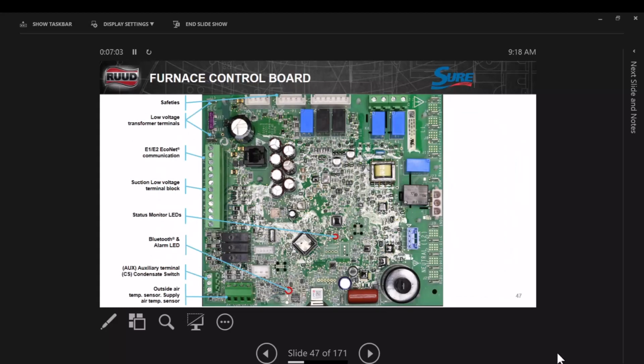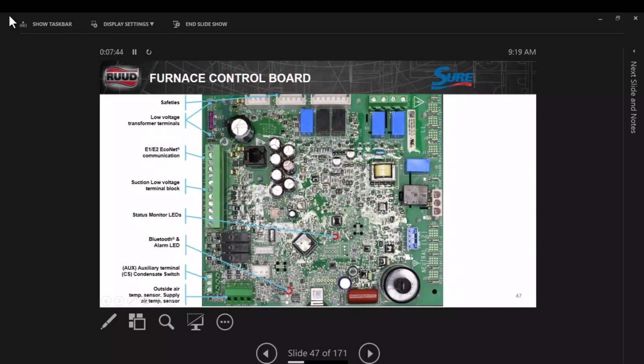On the furnace control board, you see at the top row, that's all the safeties coming in up here at the top. We have our low voltage terminals coming down the left side there. And then we have our terminal block. This is where your E1 and E2 communication circuit control is going to go, and your 24 volts to your thermostat. All that's going to go there. Right down here, you see the LEDs, the Bluetooth LEDs here. Auxiliary terminal switch. Now, the auxiliary is where we're going to hook our condensate switch up. Because this unit is a communicating unit, even though it's a regular thermostat, it's still communicating. We cannot break any of the thermostat wires. The E1, E2, R, and C, it will not allow us to do that.